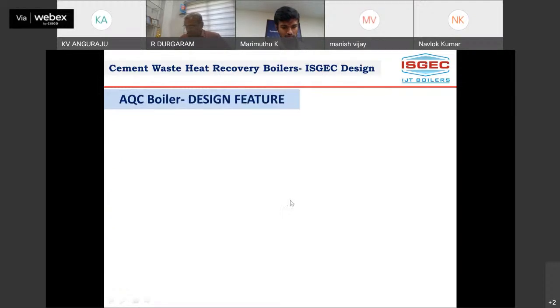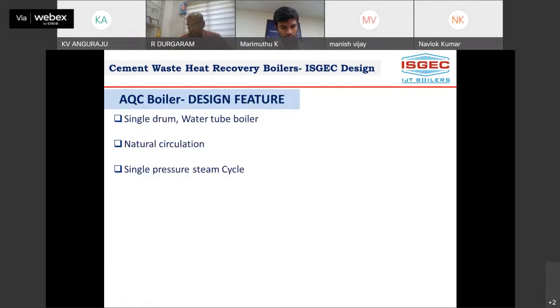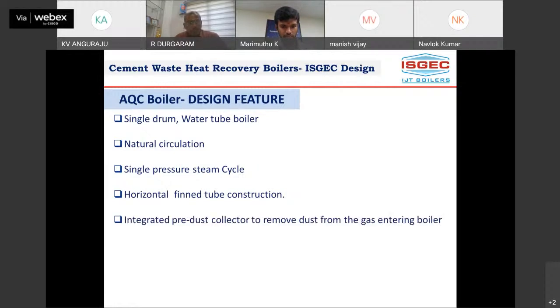This is an AQC configuration. In this also, a single drum water tube boiler, natural circulation, single pressure steam cycle, with a horizontal finned tube section so that the heat transfer areas are arranged within a limited space. Then an integrated pre-dust collector removes dust from the gas at the entry point. This is one very important piece of equipment in the AQC boiler, so that dust is collected before it enters the boiler, your heat transfer surfaces are well protected, and the life of the surface is also increased.